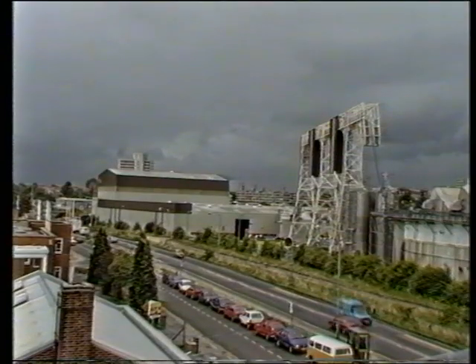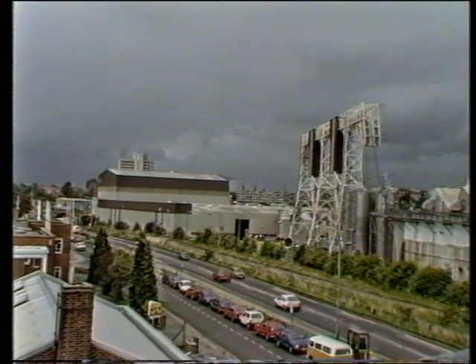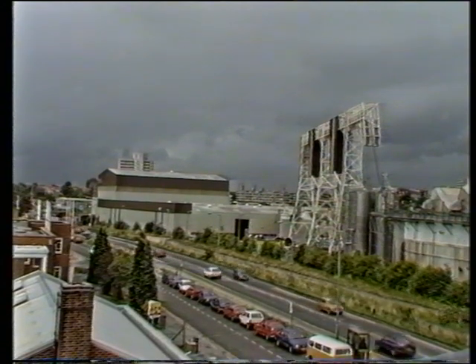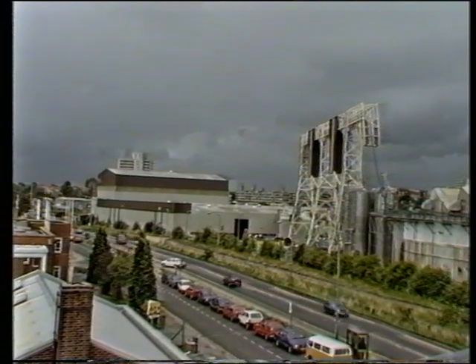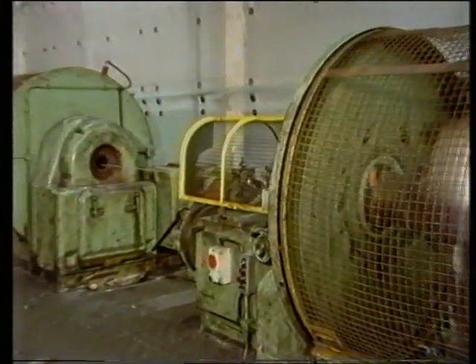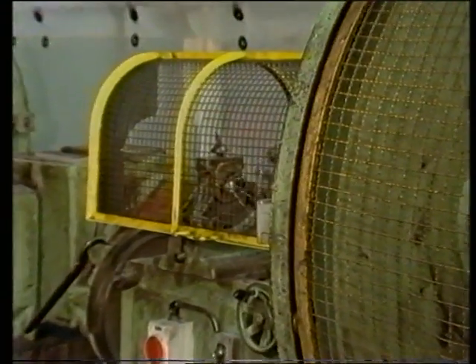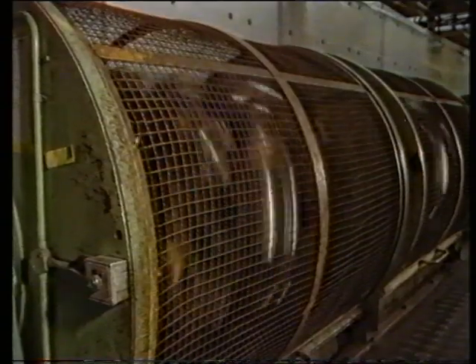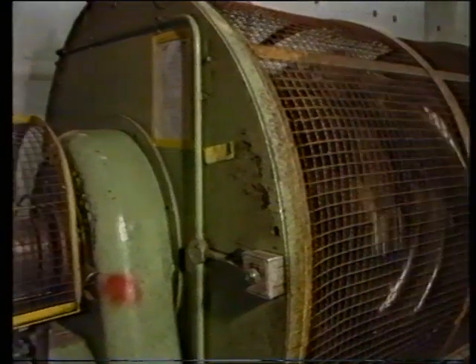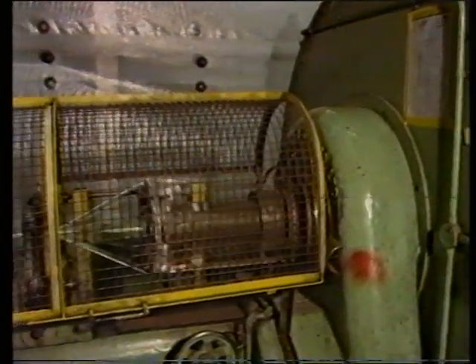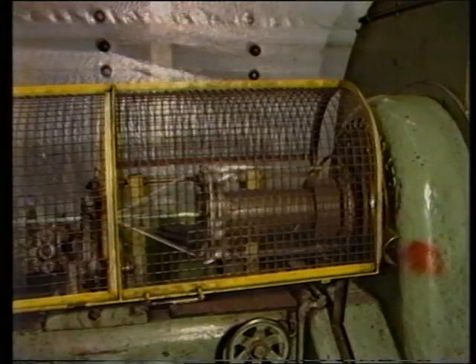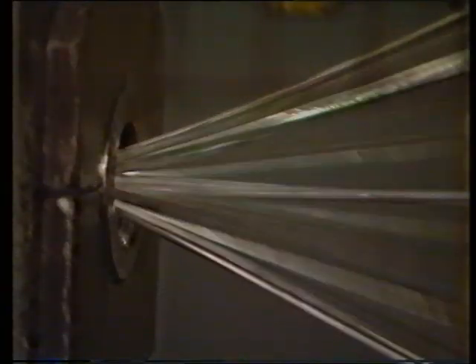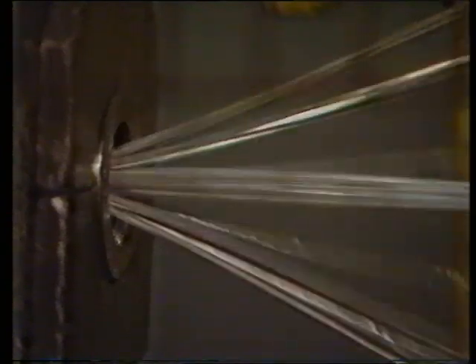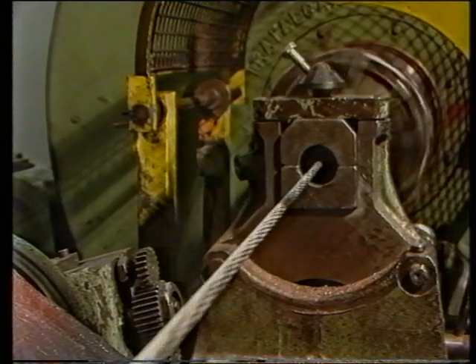The provision of that link was entrusted to Pirelli General, the British member of the international Pirelli group, world leaders in the cable-making business. Their task was to produce 60 kilometres of 33,000-volt submarine cable to carry the power from the mainland to the Scillys. The manufacture of the cable, the longest of its kind to be laid in the United Kingdom, began at the company's power division at Eastleigh in Hampshire. Here, individual copper wires are stranded together to form the 3 70-square-millimetre conductors that will go to make up the Isles of Scilly cable.